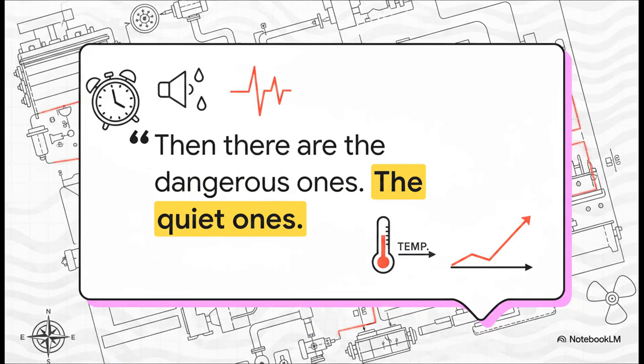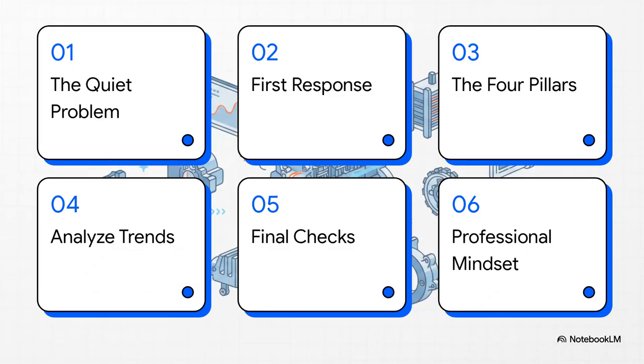You know, some problems are loud. They come with alarms, bangs, or a spray of oil. You can't miss them. But a slow creeping rise in cooling water temperature, well, that's different. That's the quiet problem. It won't always give you an alarm right away. It just drifts. But for any good engineer, that slow drift is a massive red flag. It's a sign that the whole thermal balance of your plant is starting to slip away from you. So we're going to walk through how a professional diagnoses this kind of mystery. We are going to move from pure guesswork to technical certainty.